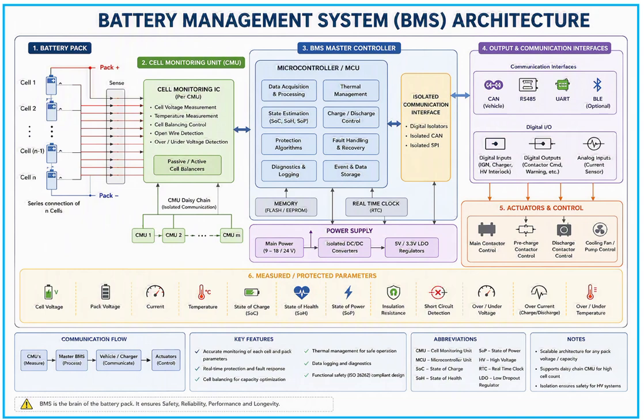Output and actuator control is managed by the BMS, which is connected to several external devices to ensure safe battery operation, actuating the main contactors, pre-charge contactor, discharge contactor, cooling fan and pump control, etc. So these are all about the battery management system, and we will look at how it works.